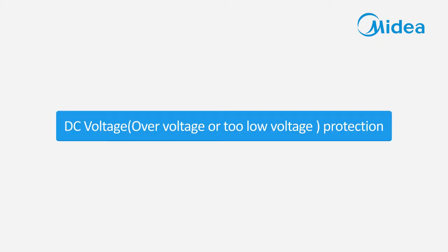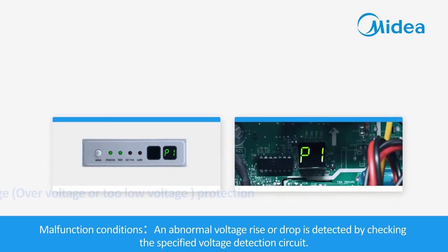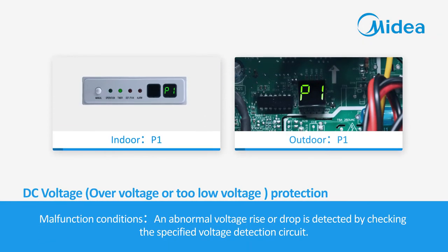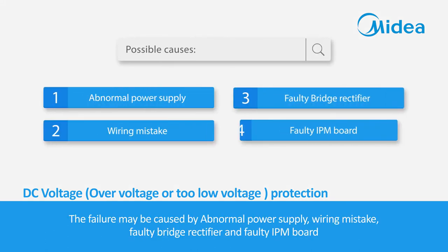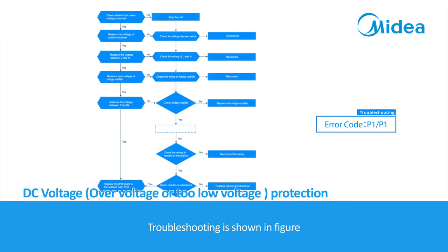DC voltage over-voltage or low-voltage protection. Malfunction conditions: an abnormal voltage rise or drop is detected by checking the specified voltage detection circuit. The failure may be caused by abnormal power supply, wiring mistake, faulty bridge rectifier, or faulty IPM board.